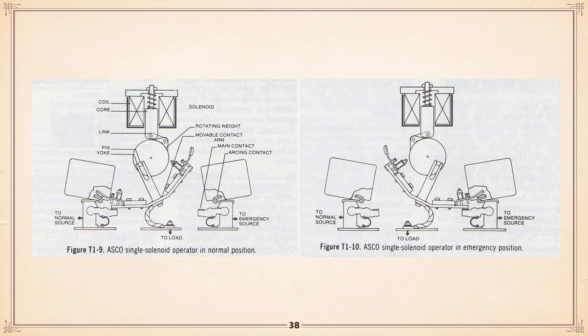It is super quick doing that. Also, it's much more compact than using motorized breakers. It doesn't have the overload protection that circuit breakers would normally have, but your gen set should have a proper circuit breaker on its output. Your power supply should have protection, etc. So you really don't need to have that protection built into the transfer switch.